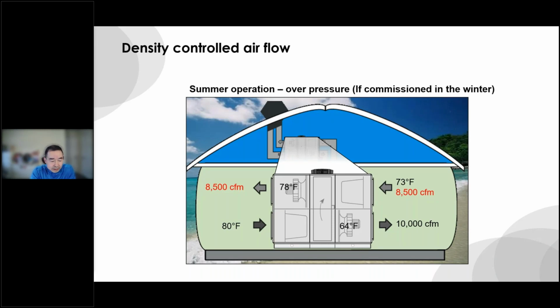So the conclusion is, we basically recommend to not only have the airflow measurement station to help you deliver the air you specify, but at the same time, you want to have a real-time temperature adjustment, so you can adjust the airflow based on the temperature. I believe this can be a good recommendation for the cold climate.